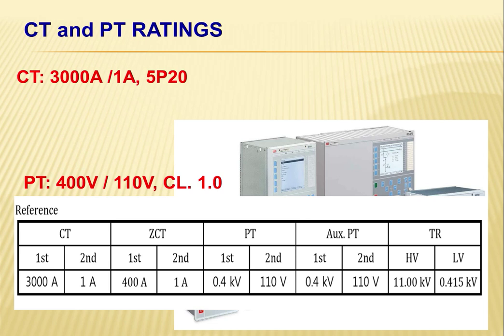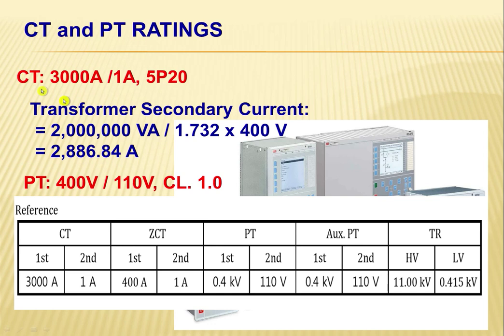So these are the ratings of our CT and PT. Our CT is rated 3000 ampere. The ratio is 3000 to 1 ampere plus 5P20, while our PT or voltage transformer ratio is 400 to 110 with class 1.0. We have here 3000 ampere because it is based on our transformer secondary current, which is close to 3000 ampere, 2886.84 ampere. We also have our zero sequence current transformer, also called CBCT, or core balance current transformer rather, and the ratio is 400 to 1 ampere.